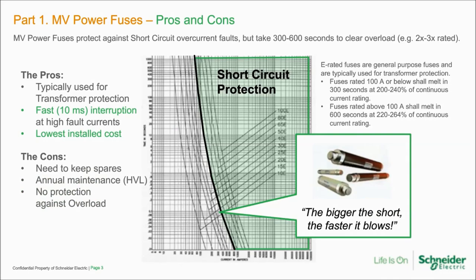Here's a fuse curve. It's complex, and a lot of times people dismiss these curves as too much information. I'm highlighting the 40E rated curve — the fuse curve for a 40E rated fuse — and you can see where 40 amps falls. It's important to note that this fuse will take 300 to 600 seconds — in other words, minutes — to burn out and clear the overcurrent.